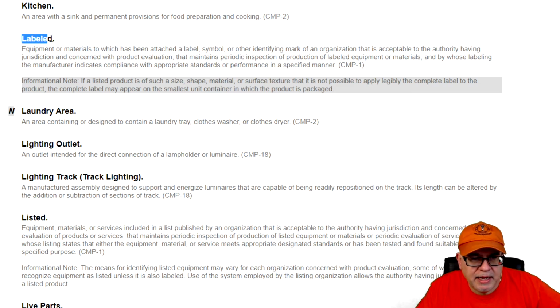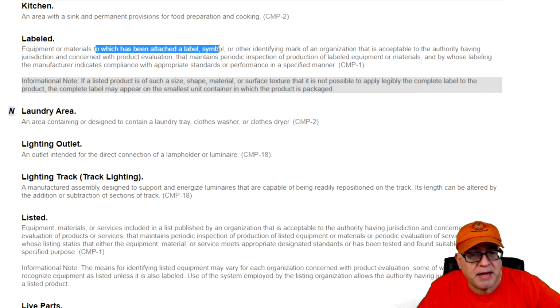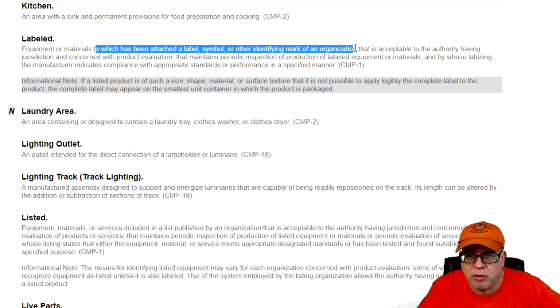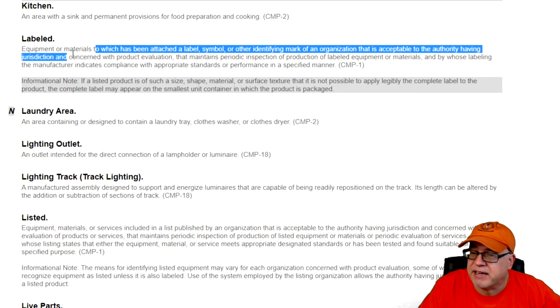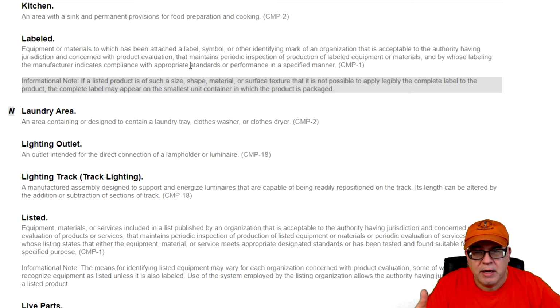Labeled, again, it's equipment or material to which has been attached a label, some kind of symbol or other identifying mark of an organization that is acceptable to the AHJ, like a nationally recognized testing laboratory, UL, ETL, which is Intertek, Met Labs, or whatever. They will apply their label, their mark, okay, and it tells us that it's been inspected, evaluated, or whatnot, and it's good to use. Okay, it meets the appropriate standard for whatever's being used.